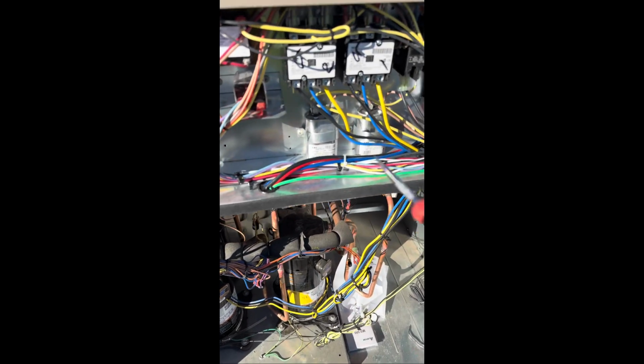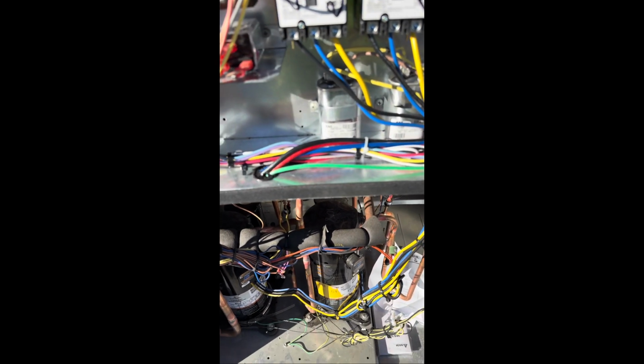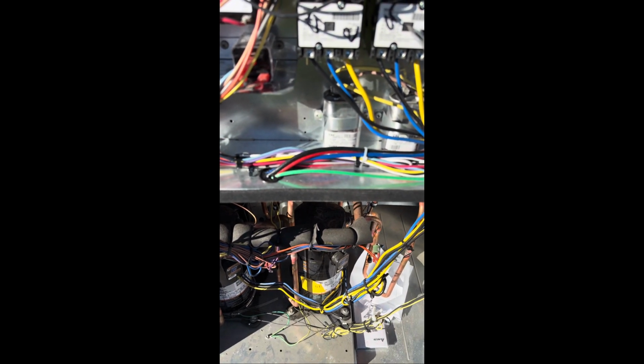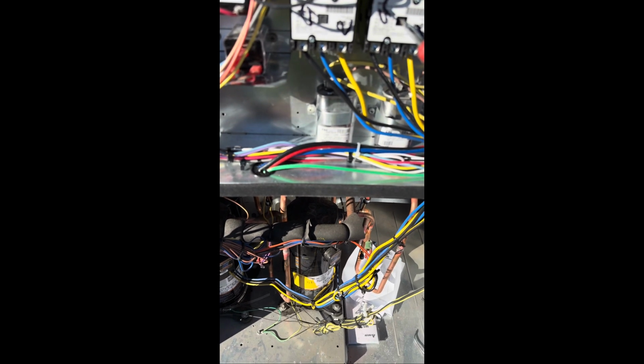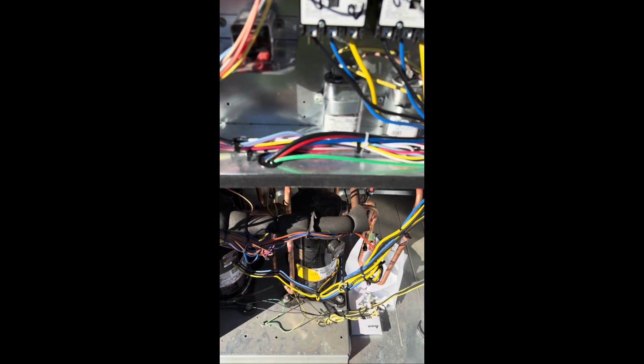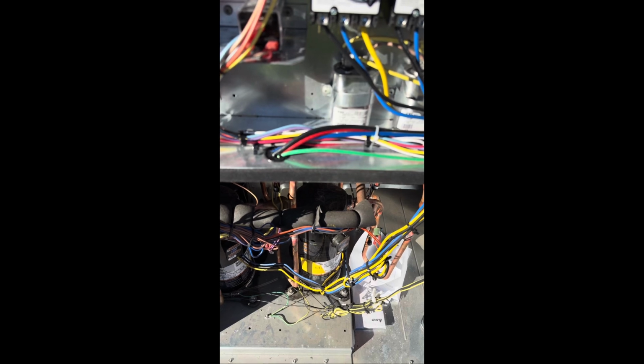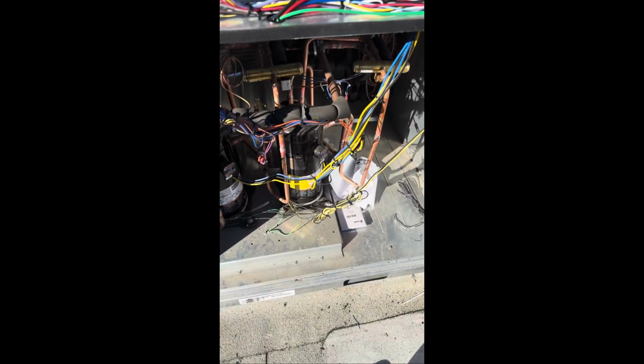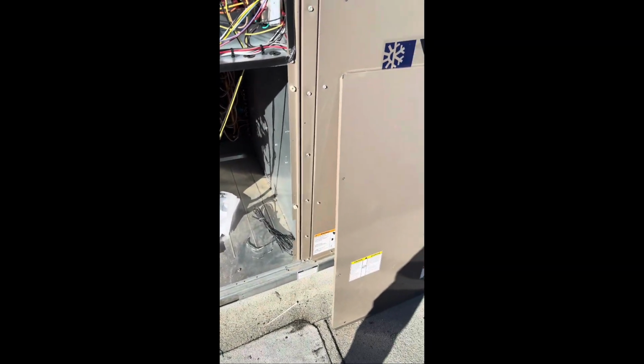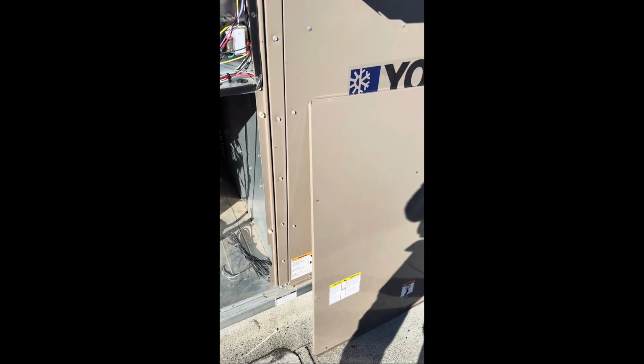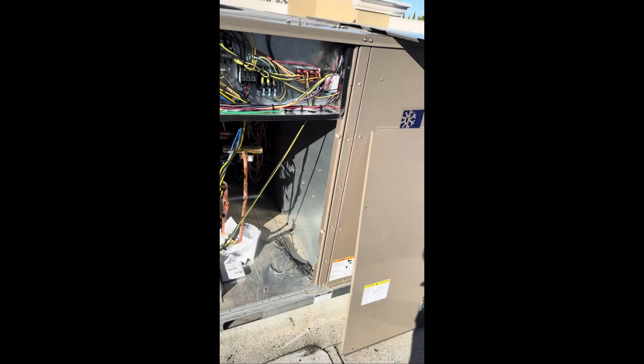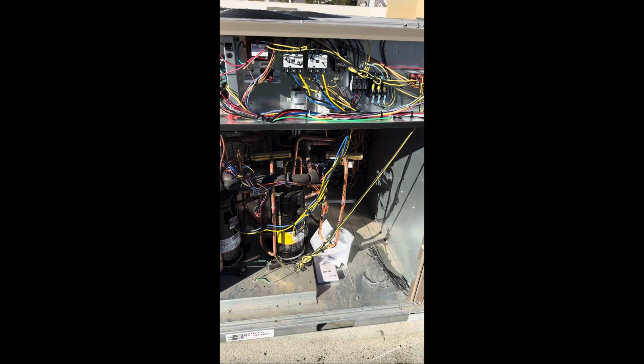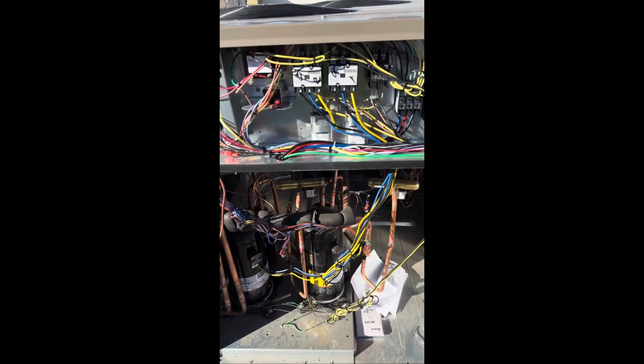And now just a quick test here. We're gonna press in the contactor and see the sound. Make sure here. Beautiful. Nice pumping compressor. Okay, so we verified that. Another thing that you can always check is making sure that the actual blower motor is running the proper way. And that's pretty much it. So we're gonna clean up here a little bit, and then we're gonna finish up for the day.